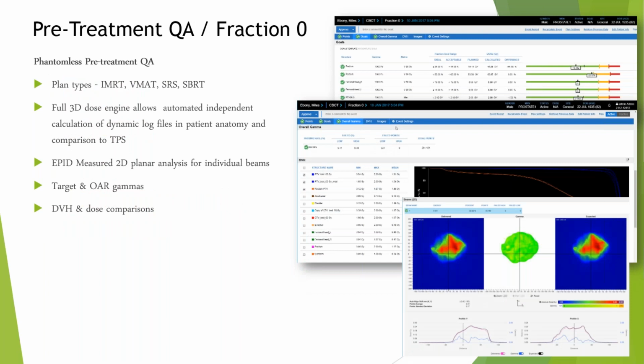Pre-treatment QA, or fraction zero, as we call it in SunCHECK, offers phantomless pre-treatment QA, and it's available for all intensity modulated type treatments. The full 3D dose engine allows automated independent calculation of log files which can be overlaid on the patient anatomy and then compared to the treatment planning system results.